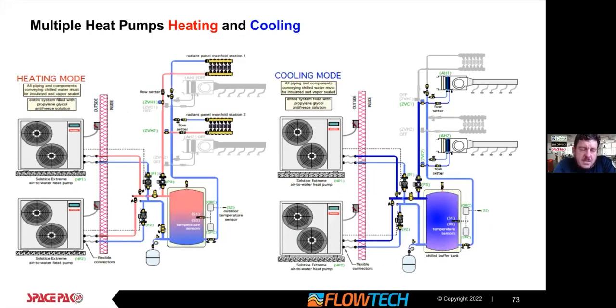A couple of key pieces here is a piping diagram for that. We've got some others as well. Key point here is to utilize the individual circulators for each unit. There's antifreeze protection protocols, and there's reasons why you need the SpacePak to operate its own circulator. So there's a 110 line voltage from each of those units coming into its own circulator. So when that unit calls on, it turns its own circulator on. Or if there's an antifreeze protocol happening, it'll turn a circulator on and recirculate buffer water temperature through the unit.